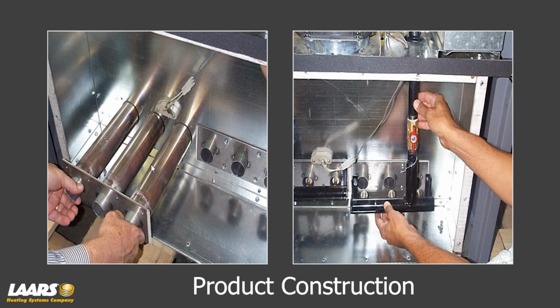Now they'll add the burners. The burners are either a 3-bank burner or a 4-bank burner, depending on the size of your boiler. What we see being installed here today is a 3-bank burner. And those burners are held into position with 4 stainless steel 5/16 screws, or you could also use a Phillips head screwdriver to remove those. Next, we'll have a manifold.